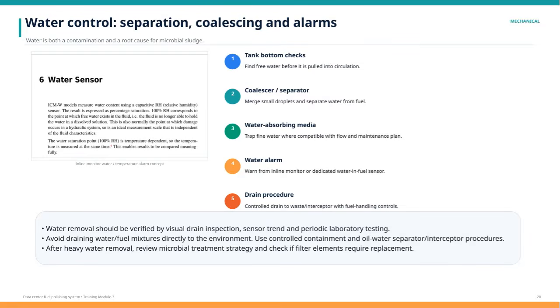Water control is essential when managing fuel systems, as water acts both as a contaminant and a root cause for microbial sludge. To effectively manage water in fuel, we use a combination of mechanical techniques and alarms. First, tank bottom checks are critical. This means looking for free water at the bottom of tanks before it gets pulled into circulation, which helps prevent contamination early on. Next, we use coalescers or separators. These devices merge small water droplets together so they can be more easily separated from the fuel, improving water removal efficiency.